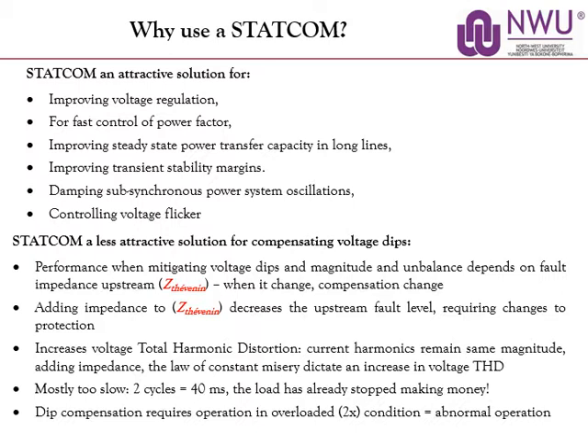But it also increases the total harmonic distortion in voltage, because remember, the load downstream is non-linear, it's controlled. It will suck in the same value of current harmonics, adding some impedance, and what do we have? The voltage distortion goes up. And it's mostly too slow. It normally takes around 2 cycles, and then the load has already stopped making money. So dip compensation requires operation in an overloaded condition, normally when they use a STATCOM, and that is abnormal. You really stress that equipment to help compensate for dips.